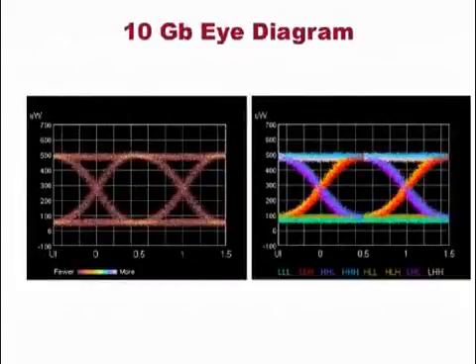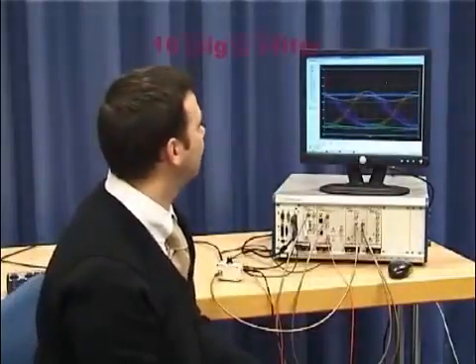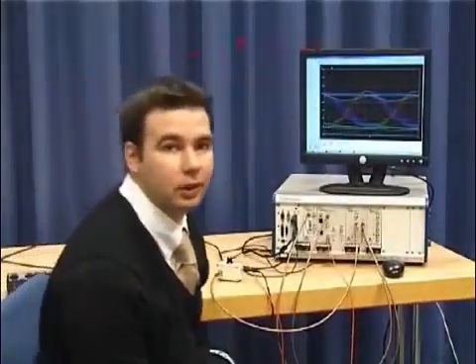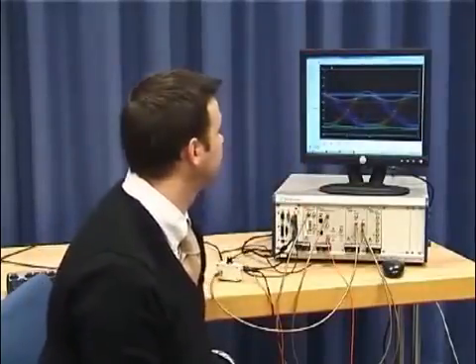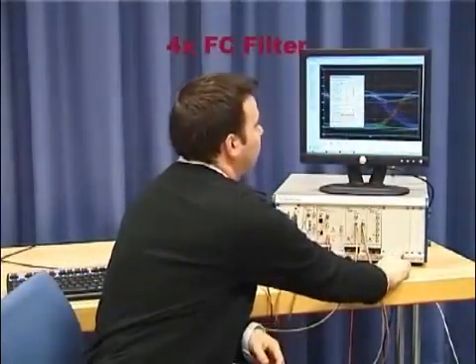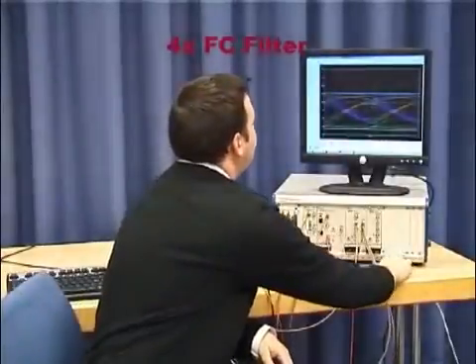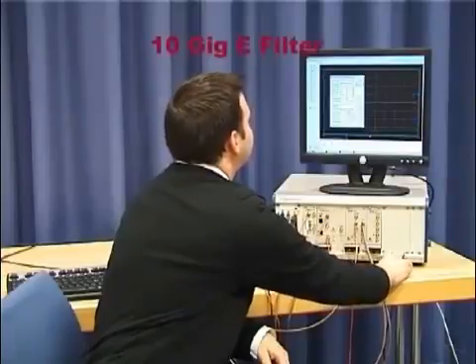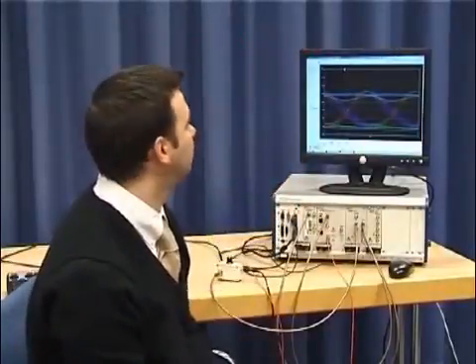Now let's have a look at the 10GIG eye. Here is our 10GIG signal — I've already set it up. If I hit Acquire, we'll see the eye updating. This is actually a K28.5 signal with a compliant 10GIG reference receiver. Just to demonstrate, I will select the 4 times Fibre Channel eye, which obviously is going to close the eye quite considerably. And now I'll jump back to the 10GIG eye. Pretty straightforward to demonstrate the new 10GIG compliant DCA.